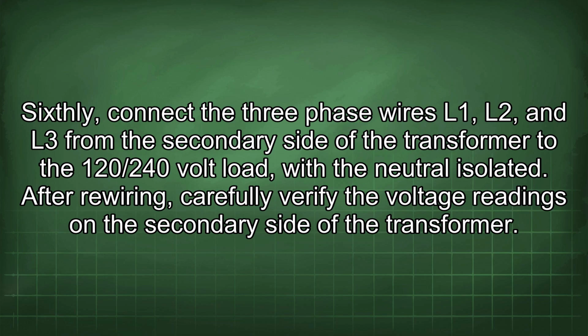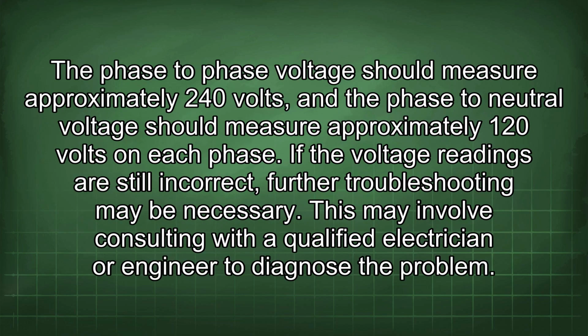After rewiring, carefully verify the voltage readings on the secondary side of the transformer. The phase-to-phase voltage should measure approximately 240 volts, and the phase-to-neutral voltage should measure approximately 120 volts on each phase. If the voltage readings are still incorrect, further troubleshooting may be necessary. This may involve consulting with a qualified electrician or engineer to diagnose the problem.